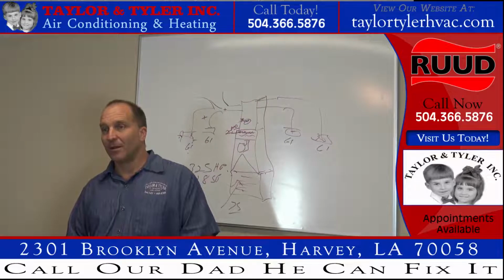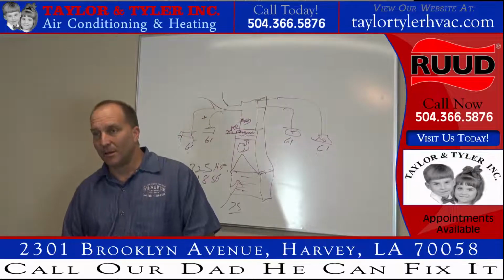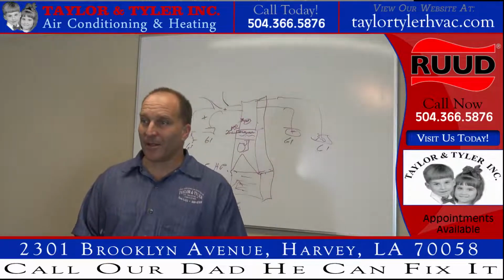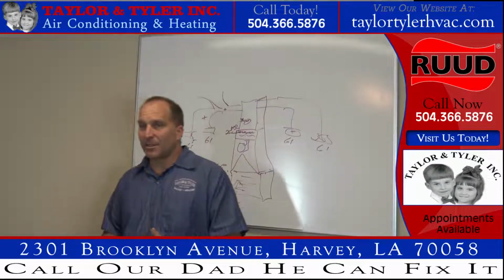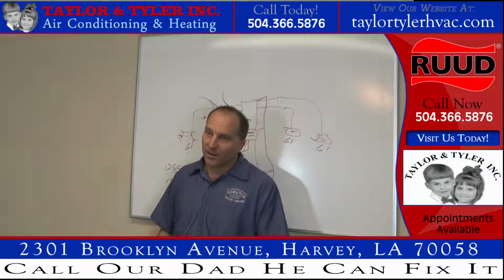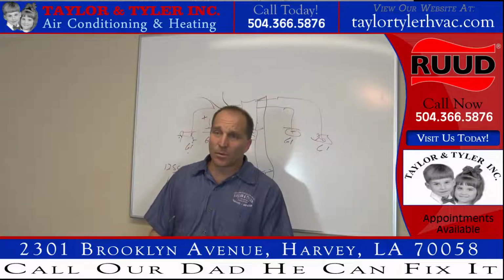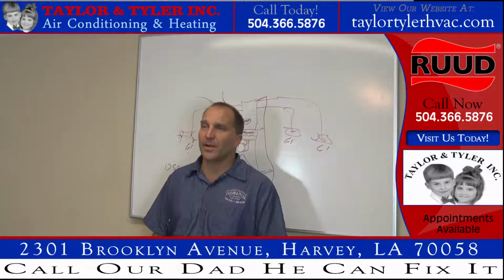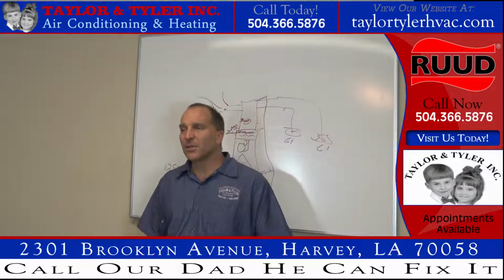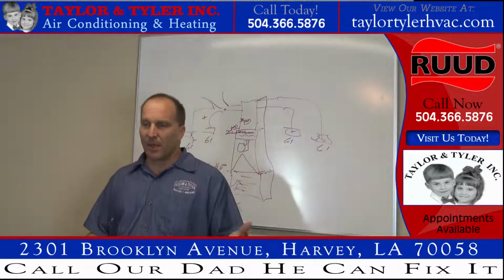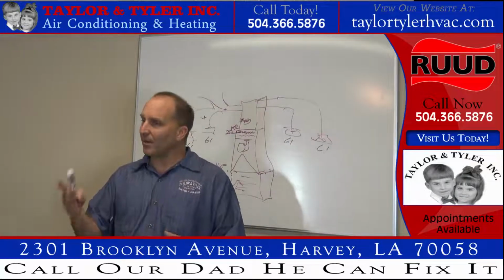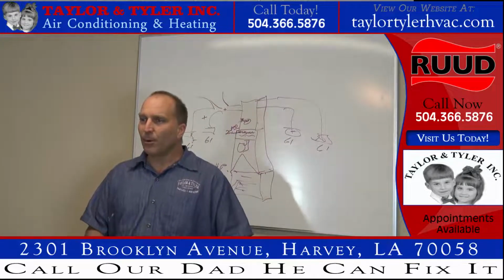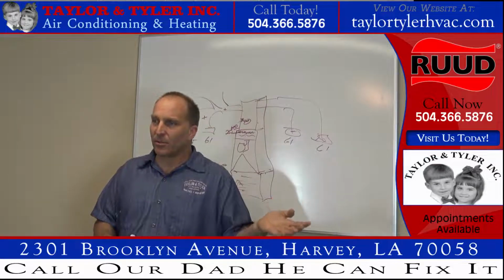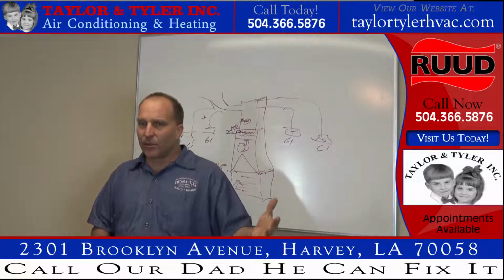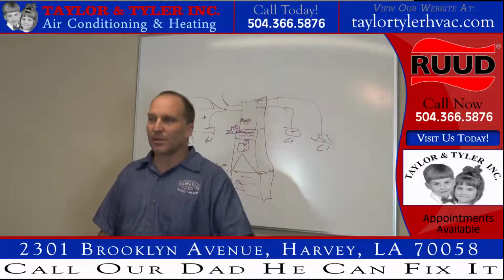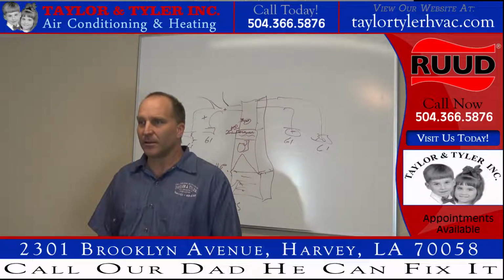And you go, man, the superheat is high on this thing, and my suction pressure is low. I got my subcooling right, but I can't get my pressures right. How can I get my suction pressure up? Well, Adam, watch what I'm saying. If your superheat is high when it's supposed to be low, and your suction pressure is low, you've got a restricted TXV. Go change your TXV, right?